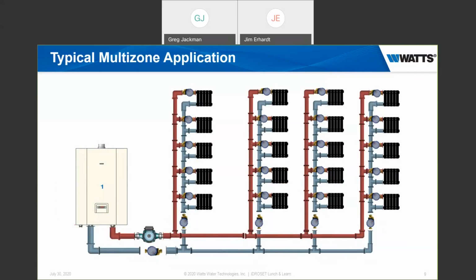So on this, you'll see we have a heat source on the left. We have a common system pump. You will see there are 4 risers going from left to right, and each one of those risers has 5 radiators. So as we look at each riser, the lowest radiator is the shortest path between the supply and the return line. The supply line being the red, the return line being the grayish color. So if we had no balancing valves on that vertical riser, the flow would go mostly through the path of least resistance, which is going to be the bottom 1 or 2 radiators.